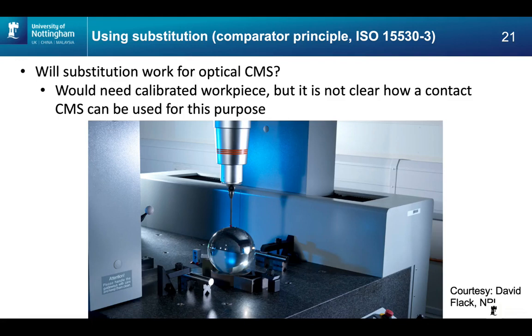So if we look at substitution, which is probably one of the easier methods to find uncertainty, and we can apply this with optical systems, this is where we basically take an object. If we're measuring, for example, the diameter of the sphere here, we put as close as possible to the object we're measuring a length standard with the same or very similar diameter. So we can effectively set the instrument up as a nulling system, and in that way we knock out a lot of the common systematic errors.